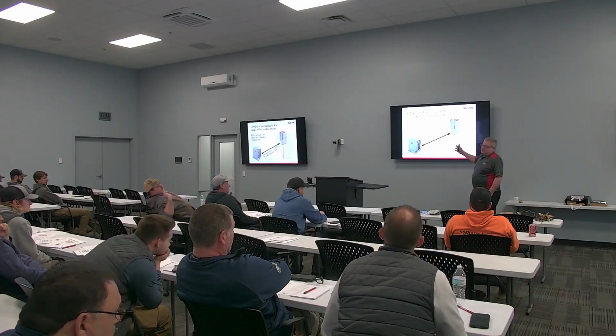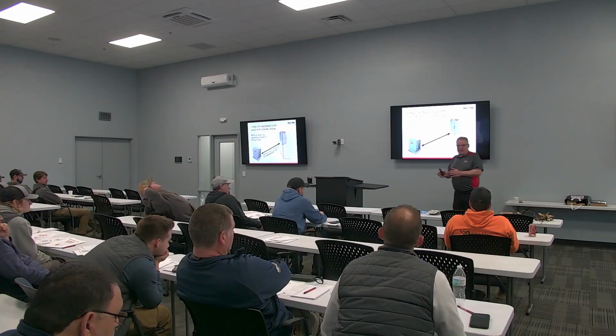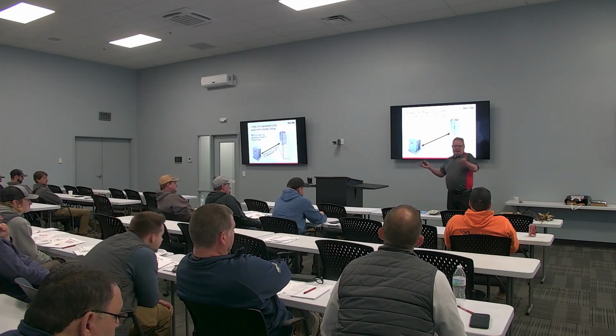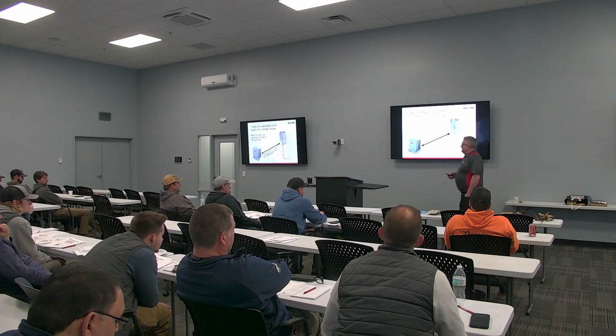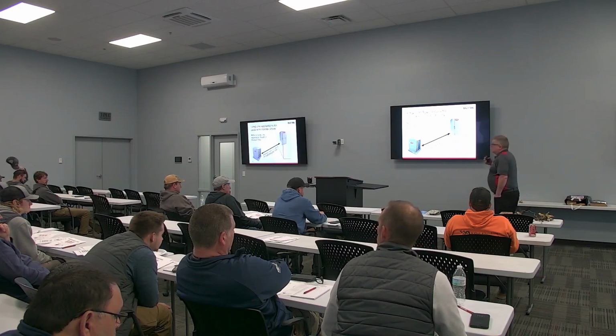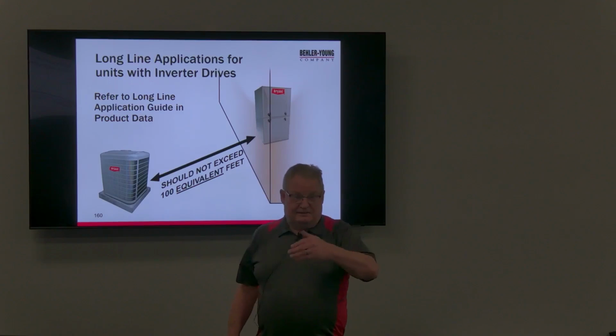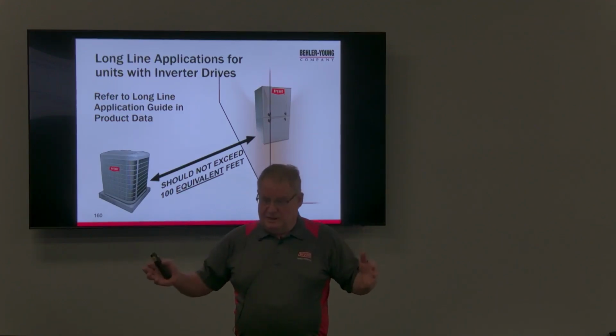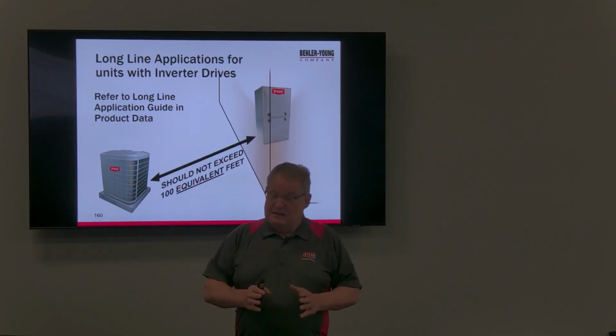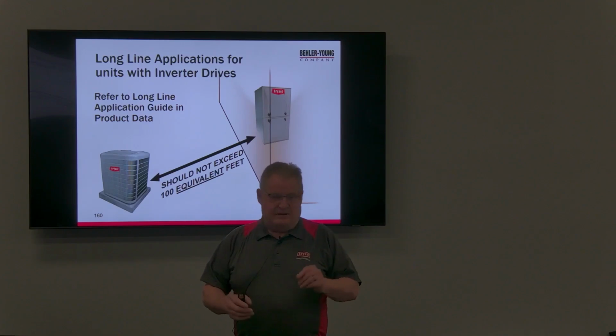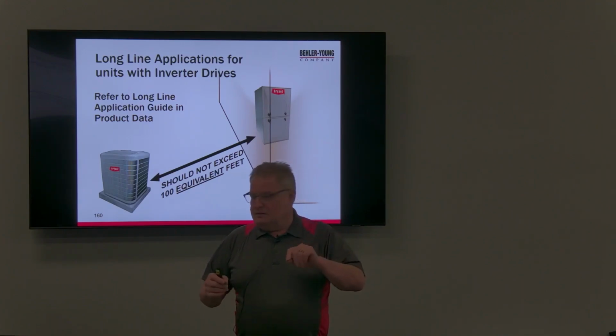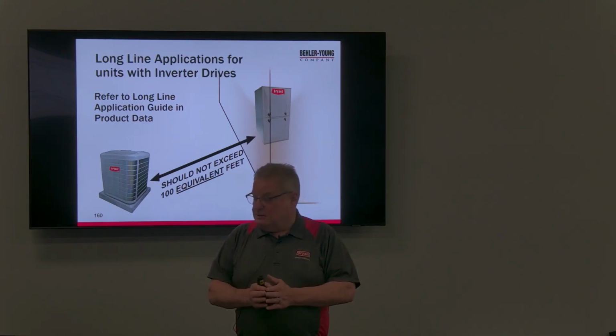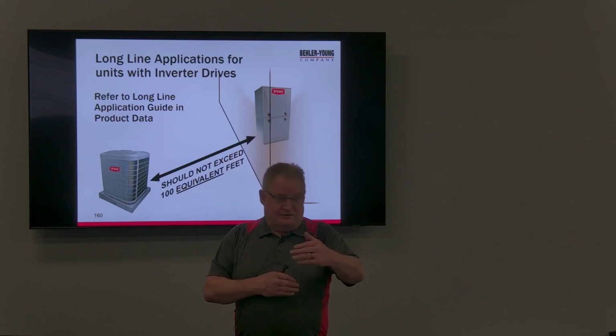These here, if I go long, you might find out in the long line guide I lose 1% capacity. Okay, so I can live with that. There are some exceptions to this. As we talk about the condenser unit being pre-charged for 15 feet of line set, you're pretty much used to that. It's not always the case anymore. Sometimes they can't hold that much because they go to the new coils, so they might not be able to hold a whole charge. So pay attention to your installation instructions.